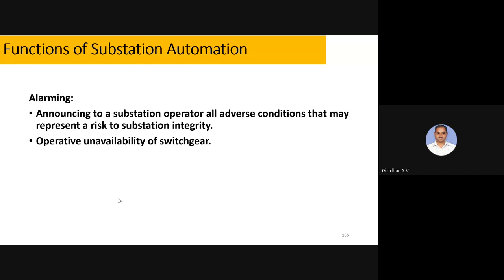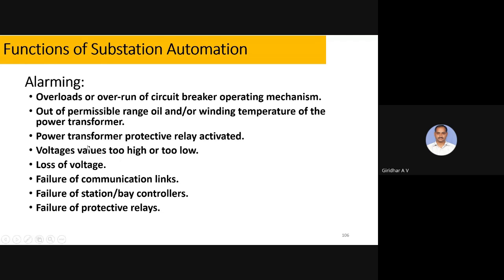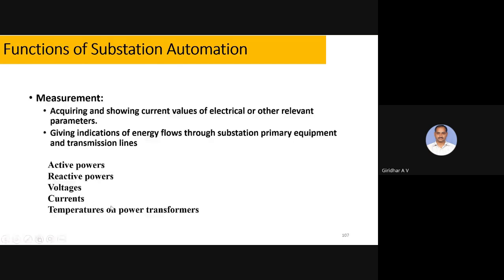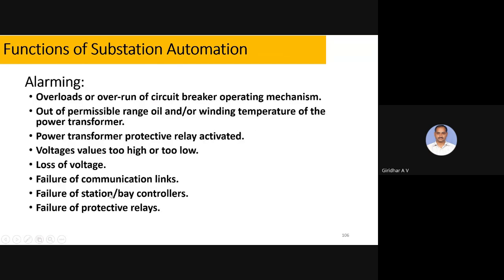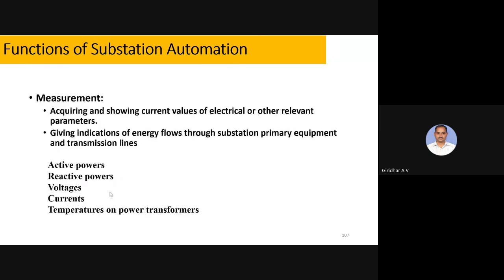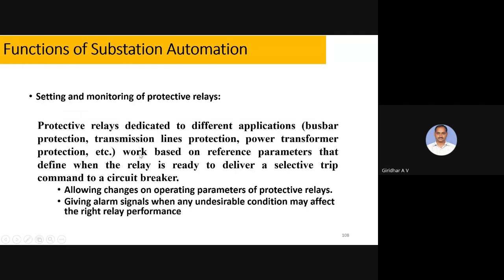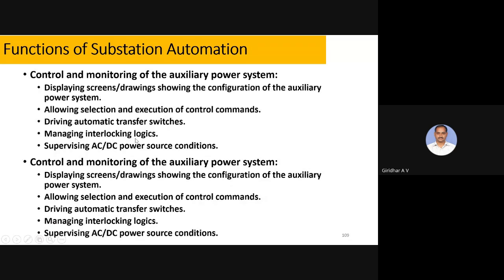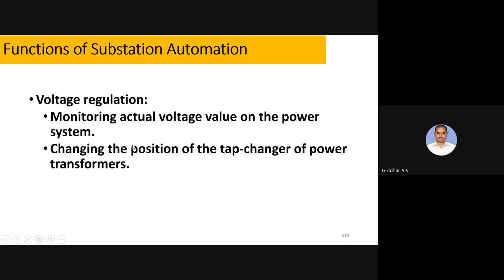Alarm annunciation. So if there is any power transformer protection relay activated, overloads or overrun of circuit breaker mechanisms, loss of voltage, or failure of communication links, alarming can also be given. There are also different suppression techniques in the alarm, depending on which is important and in what way; depending on the application aspects, we can use these alarming techniques. Then voltage regulation aspects: changing the position of the tap changer of power transformers at the appropriate time.